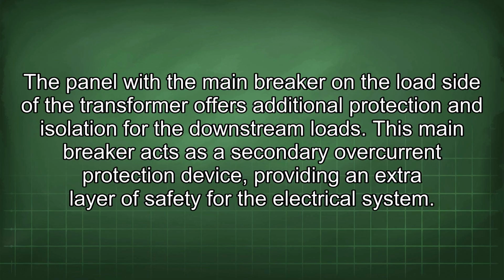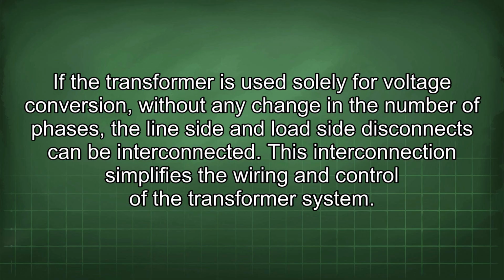The panel with the main breaker on the load side of the transformer offers additional protection and isolation for the downstream loads. This main breaker acts as a secondary overcurrent protection device, providing an extra layer of safety for the electrical system. If the transformer is used solely for voltage conversion, without any change in the number of phases, the line side and load side disconnects can be interconnected. This interconnection simplifies the wiring and control of the transformer system.